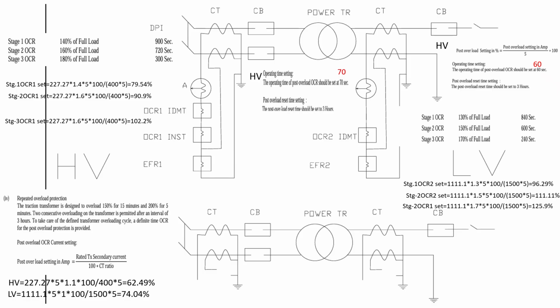So, we have seen the setting of relay with CT. All are current relays. One is instantaneous, one is IDMT, and one is restricted earth fault relay. In one numerical integrated relay, we have assembled all the settings. The rest settings are in HV: stage 1 OCR set at 140% of full load, stage 2 OCR 160% of full load, and stage 3 OCR 180% of full load.